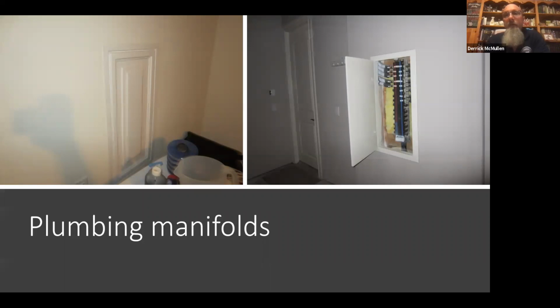1/8-inch plastic doesn't meet the equivalent of 1/2-inch gypsum. The one on the right, they took more or less a cabinet door and made it to fit that. It's solid wood, it's thick. I don't know what kind of wood it is, it's been painted. So my comment simply was that it could not be verified that this cover met fire separation requirements.